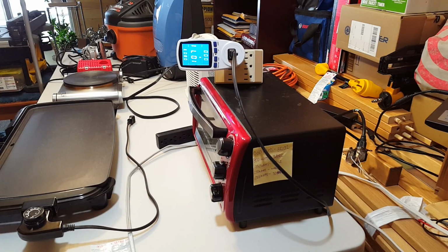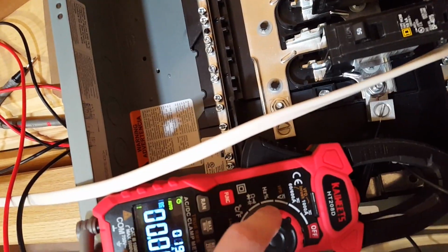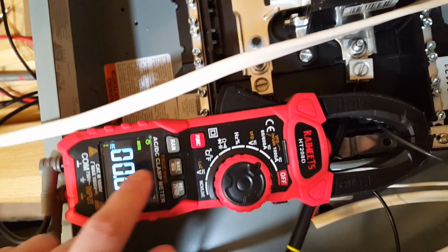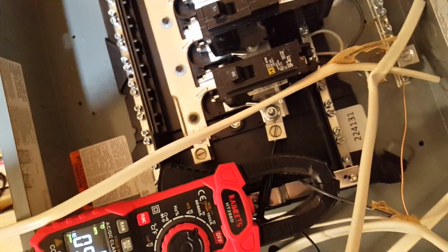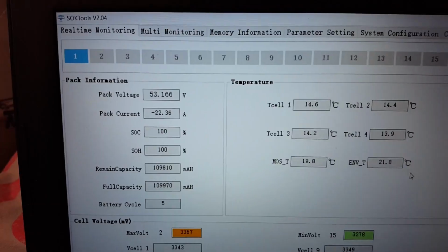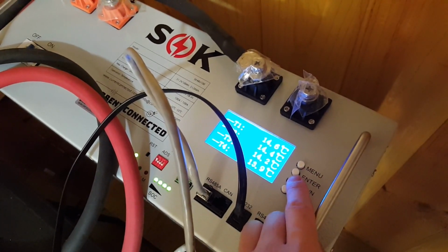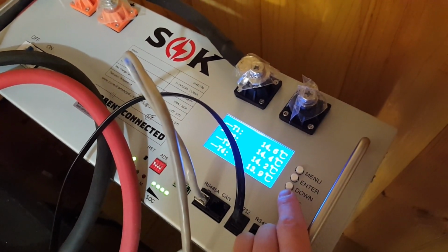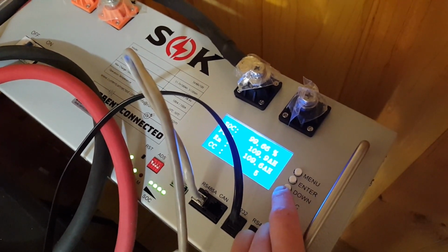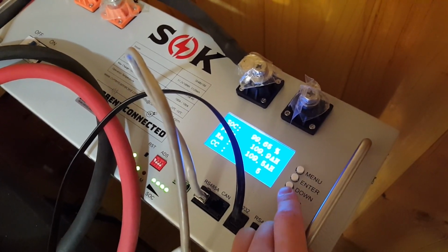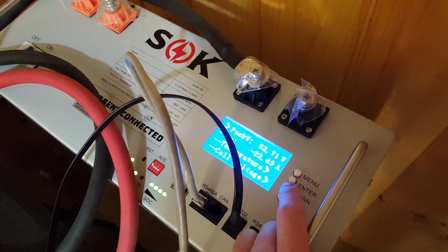Let's switch this to battery mode by disconnecting the AC input. We're in battery mode. AC amps over here. Switch to AC amps. 9.4 amps. On the DC side, let's have a look at that as well. From the battery, the software is showing 22 amps. Temperatures right now, 20 for the BMS, around 14 for the cells. Charge status, 99.6. So basically it's a full charge. We're starting from a full charge.